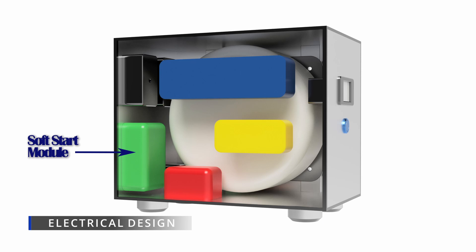The soft-start module will feed power to the transformer in a gradually increasing manner. Full power will be supplied at about 2 seconds from powering on. The isolation transformer has two separate windings, the input winding and the output winding, there is no electrical connection between the two windings. As the ratio between the two windings is 1 to 1, the output voltage will be the same as the input voltage. The transformer used in this device has a rating of 3 kVA. Hence, the maximum output current is about 13 amps.